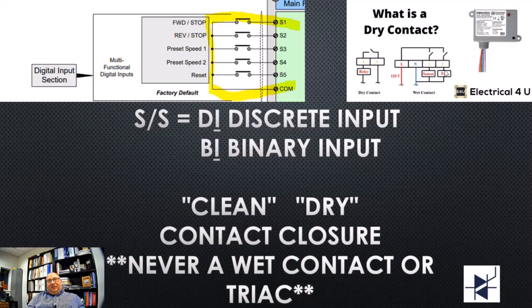You need an isolated relay for a particular switch that it needs to make on its own, independently. So we call that a dry contact closure. We don't share it with anything else. That's the symbol of a triac right down there. And this is what a wet contact looks like.